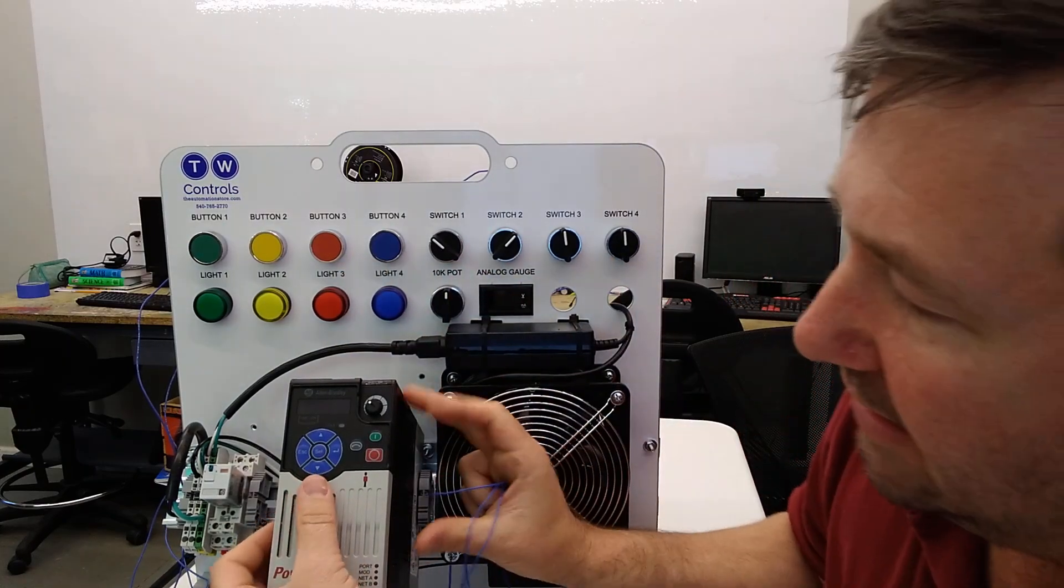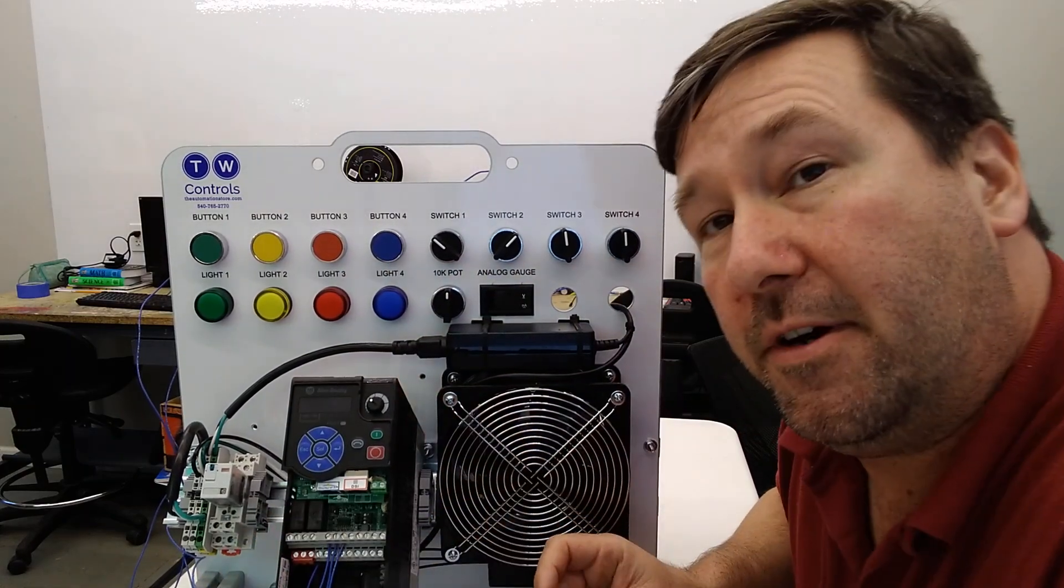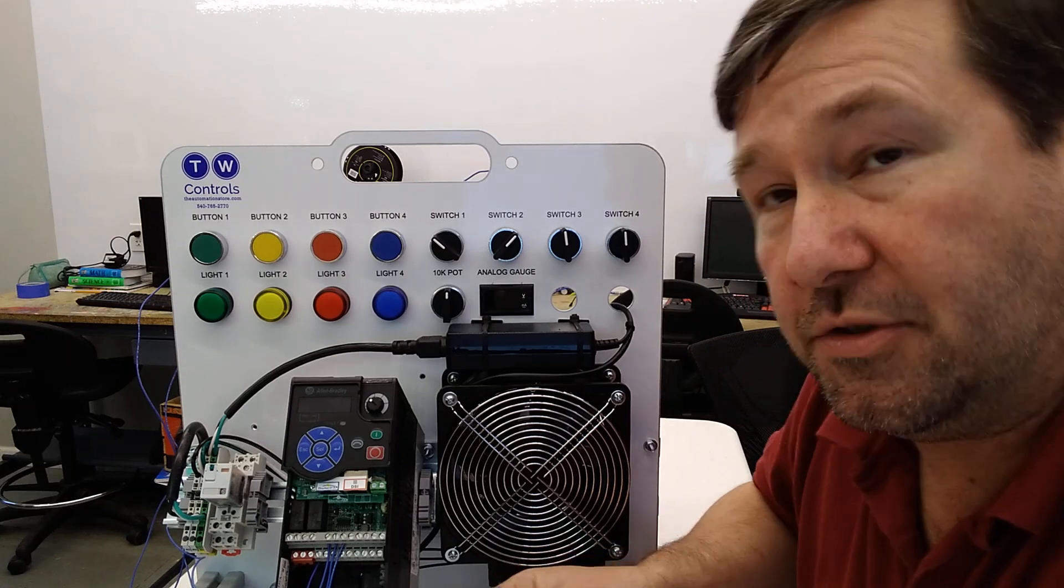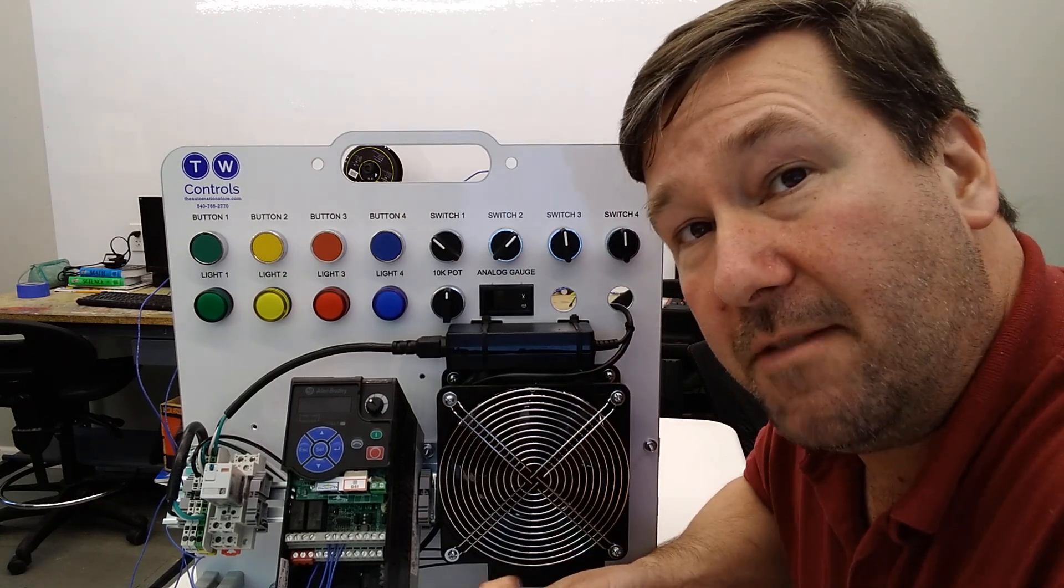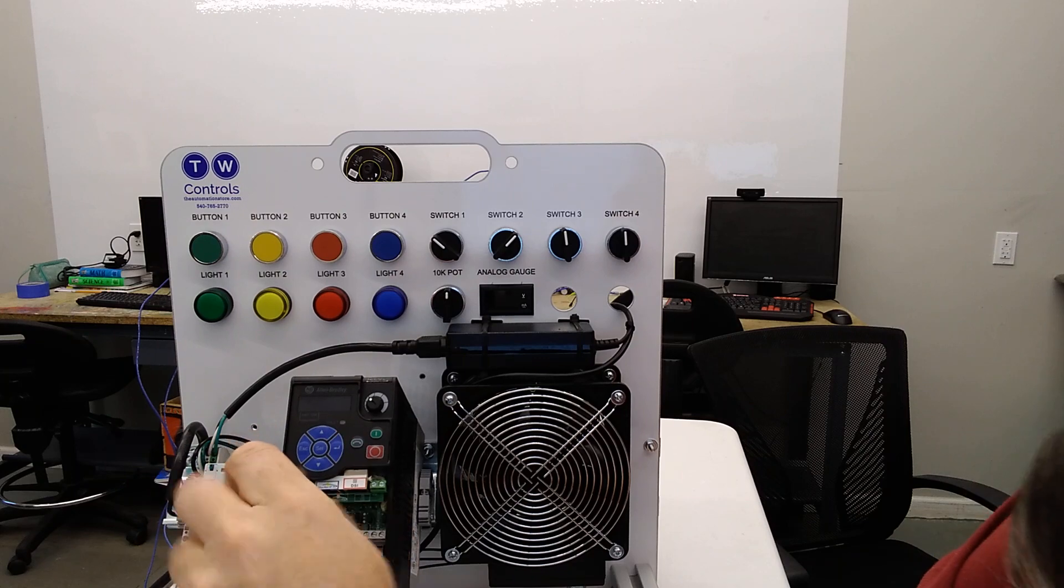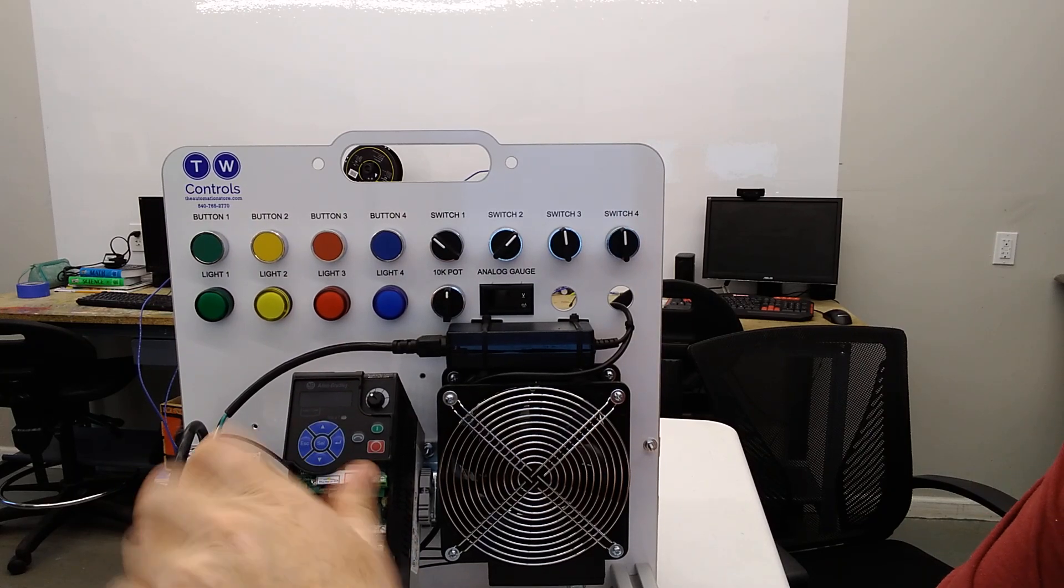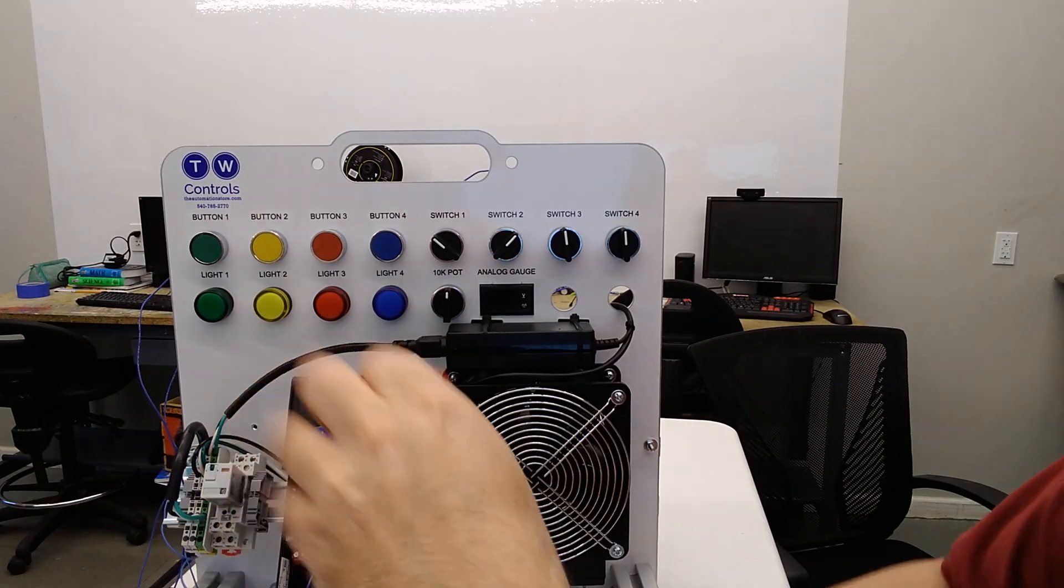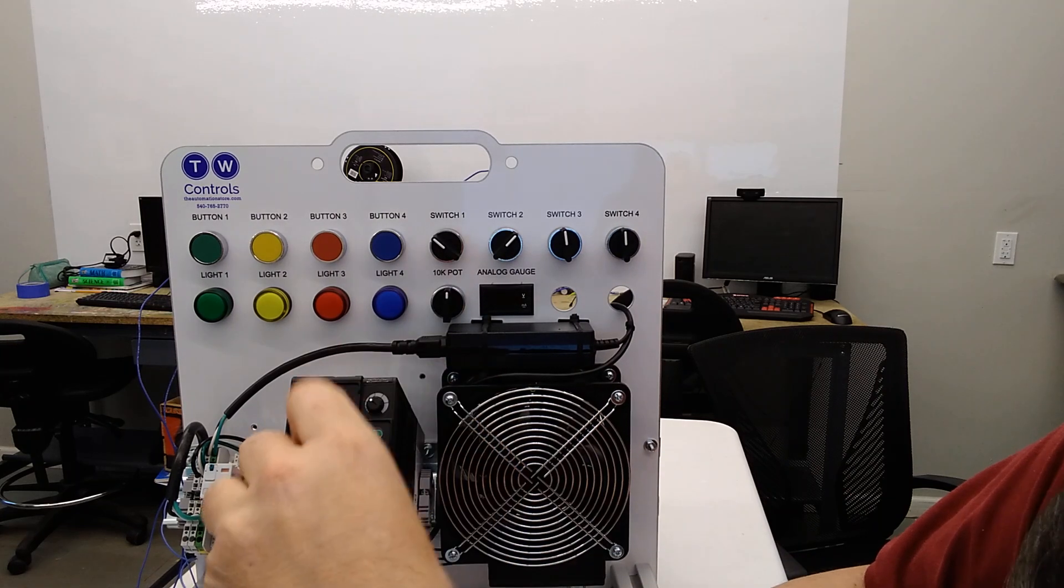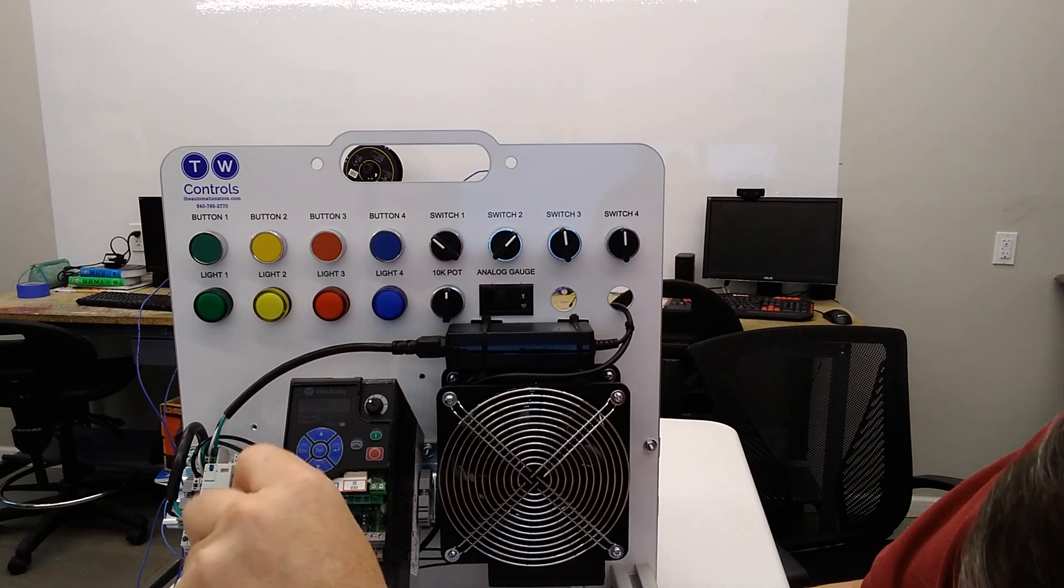We're going to slide the cover off here and we're going to connect wires to terminals 12, 13, and 14. 12 is our plus 10 volt DC, 14 is the analog common, and 13 is the analog input.